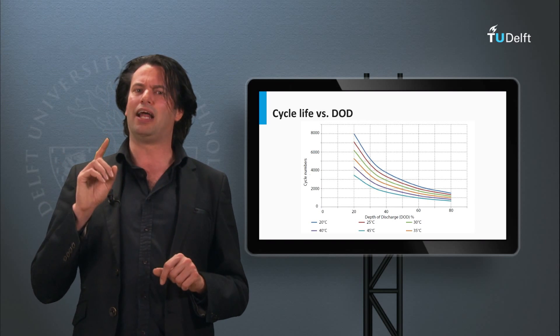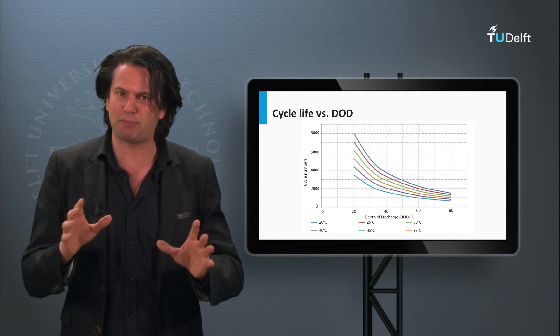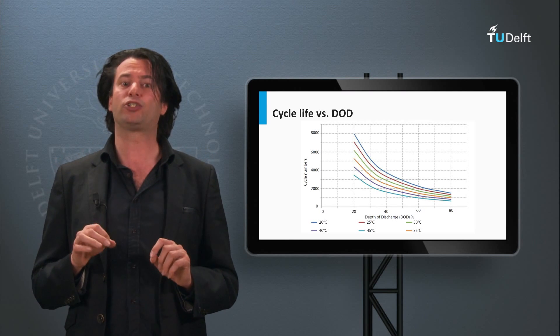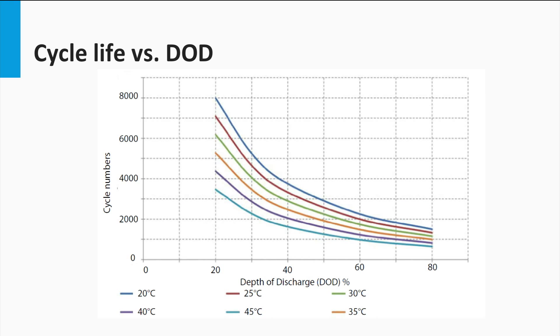Now the cycle life depends heavily on the depth of discharge until which those charge cycles last. Also, it depends on temperature. This can be seen in the graph shown here for a typical maintenance-free lead-acid solar battery. Clearly, the battery lasts longer under colder temperatures of operation. Furthermore, for a particular temperature, cycle lifetime depends non-linearly on the depth of discharge or DOD. The smaller the DOD, the higher the cycle life.